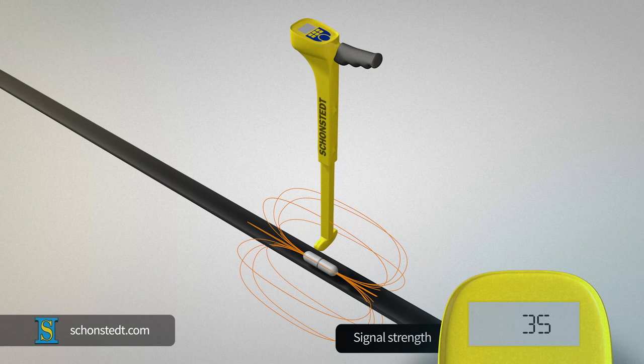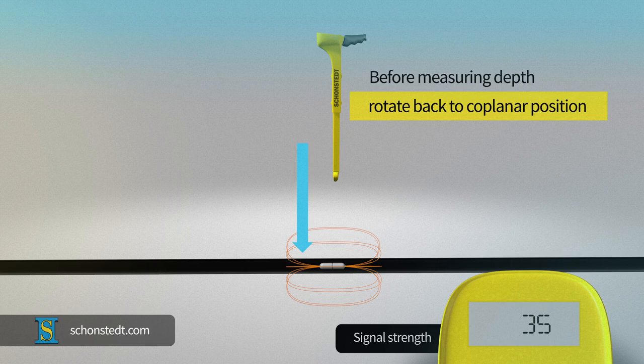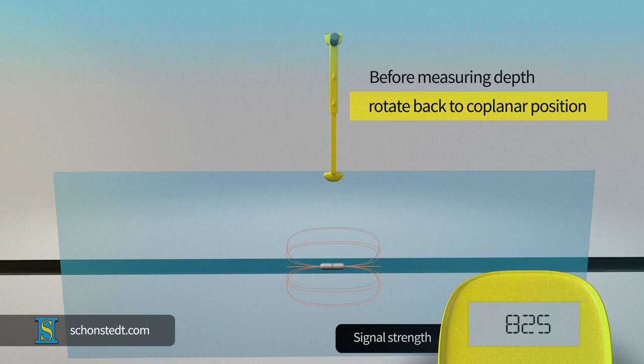At this time, you can attempt to measure the depth with the receiver, but you must remember to rotate the receiver back to a coplanar position, when the signal is strongest, before measuring the depth.